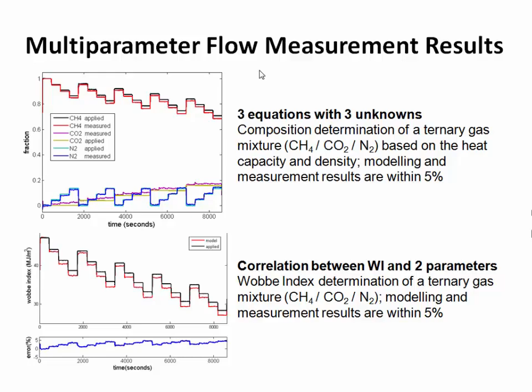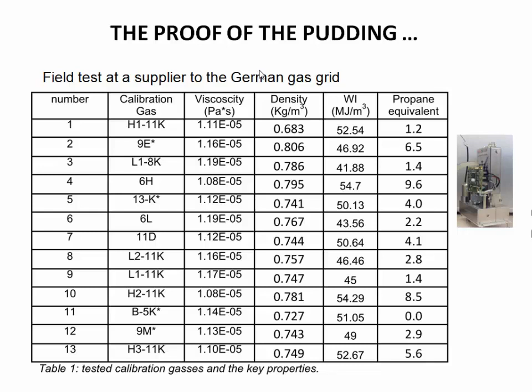And of course, the proof of the pudding is in the eating. So again, we went to this supplier of the German gas grid who has in stock these 13 different natural gases, and they are all fed into the German gas grid. And with our system, we did a measurement. So here you see these red dots are these 13. We measured 11, so these 11 different gases. And the Wobbe index we obtained from the density and from the heat capacity, again within an accuracy of 5%. So we were very happy because we didn't tune anything with the system. We just built it and did the measurements.